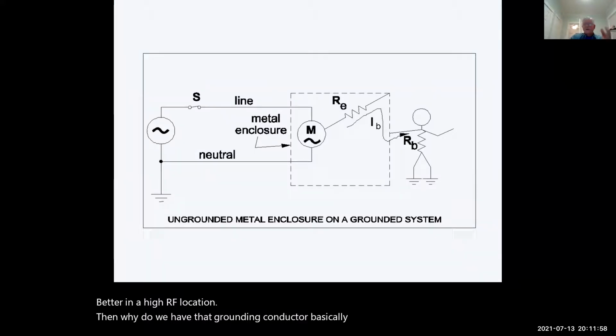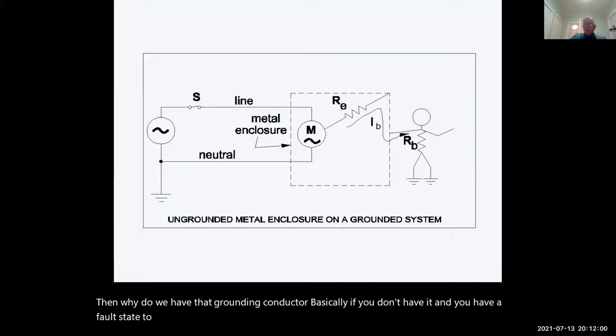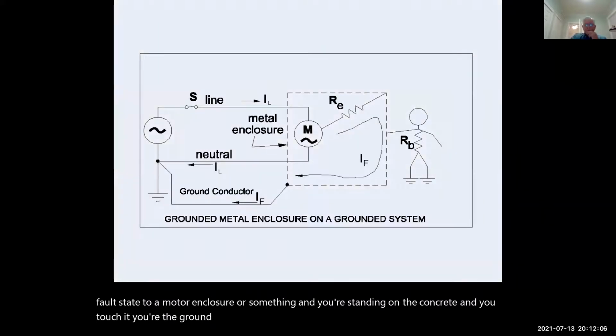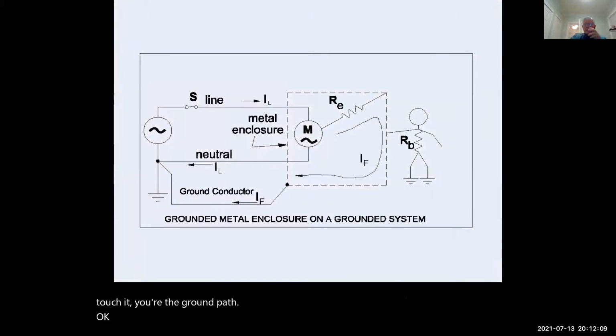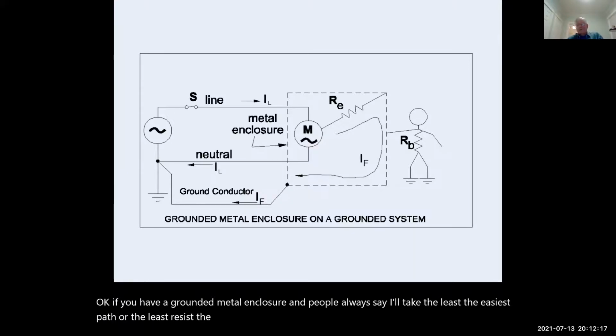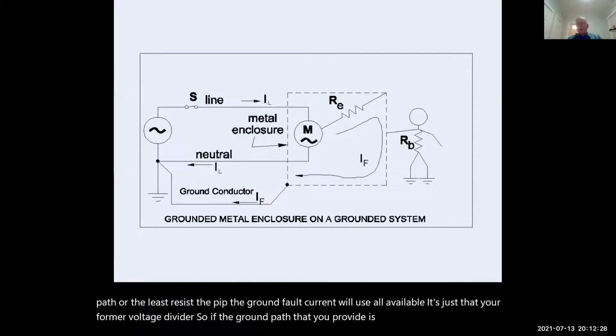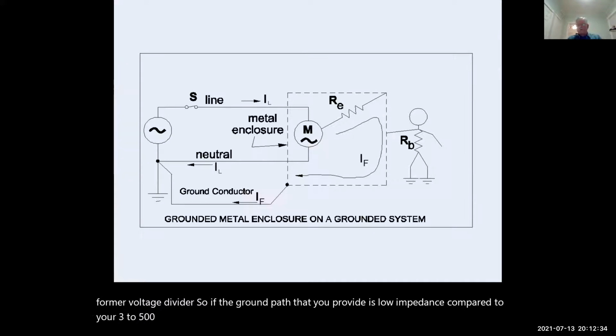And why do we have that grounding conductor? Basically, if you don't have it and you have a fault, say to a motor enclosure or something, and you're standing on the concrete and you touch it, you're the ground path. Okay, if you have a grounded metal enclosure, and people always say, well, take the easiest path, or the least resistant path. No, the ground fault current will use all available paths. It's just that you form a voltage divider. So if the ground path that you provide is low impedance compared to your 300 to 500 ohm body impedance, then you'll just get a little tingle.